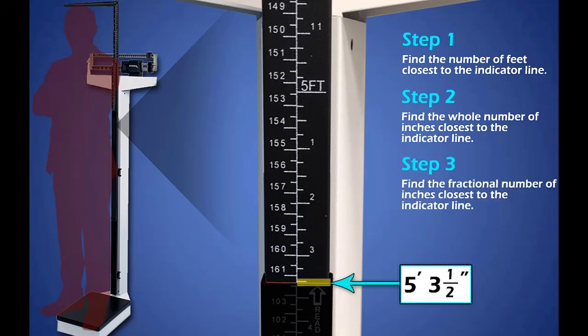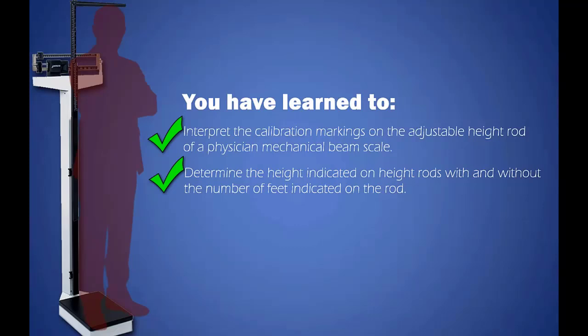Step 3. Find the fractional inch closest to or on the indicator line. In this case, it is 1/2 inch. And step 4, document the final result. In this case, you will document the height as 5 foot 3.5 inches. And there you have it. You have learned to interpret the calibration markings on the adjustable height rod of a physician mechanical beam scale, and determine the height indicated on the height rods with and without the number of feet indicated on the rod.